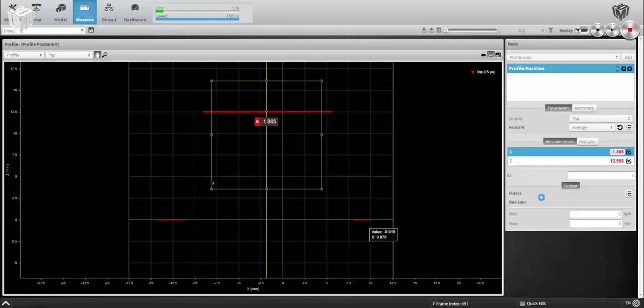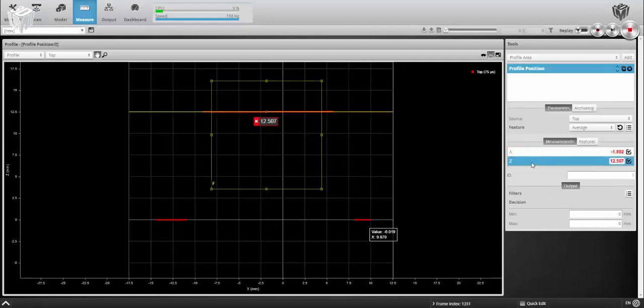By sliding the metal connector underneath the line profiler, you can see that we're now outputting a height of 12.5 millimeters for that connector, which is correct.